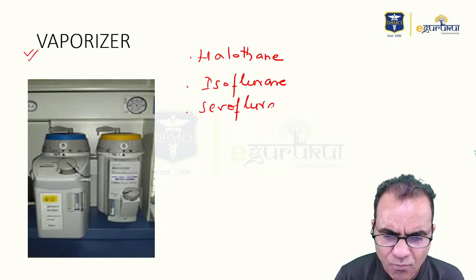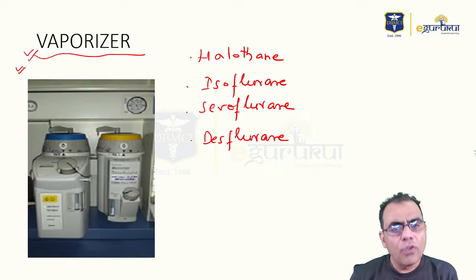Then another important component of the anesthesia machine, I told you, is the vaporizer. Vaporizers are used for the delivery of volatile agents, inhalational agents. The four volatile agents which are commonly used nowadays are halothane, we'll discuss all in detail, halothane, isoflurane, sevoflurane, and desflurane. So these vaporizers are used for the delivery of volatile agents.